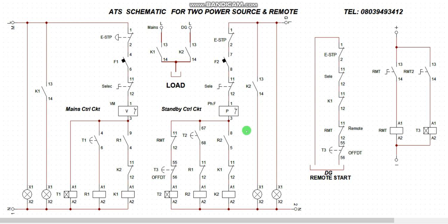One, like I said before, is by pressing the remote to shut it down, pressing this button to activate this coil and knock off this contact and this contact at the same time, simultaneously. Remember that the genset has a cool down function from the control panel. So when you shut down the contactor and also knock off the start signal, the genset will not shut down automatically. It will wait for a few seconds, perhaps 3 minutes before shutting down, or 2 minutes, depending on your configuration, okay?